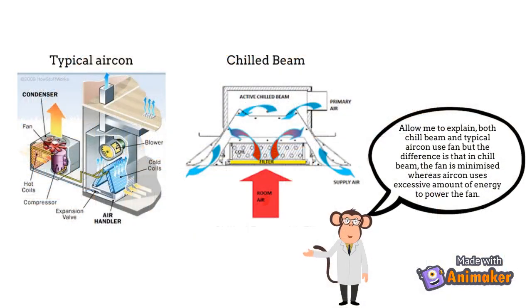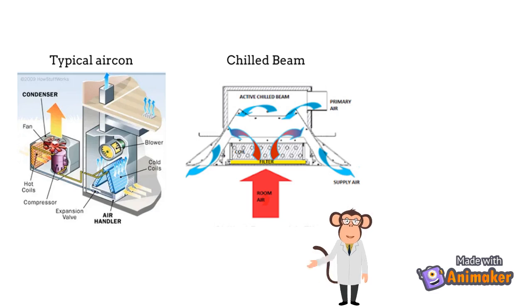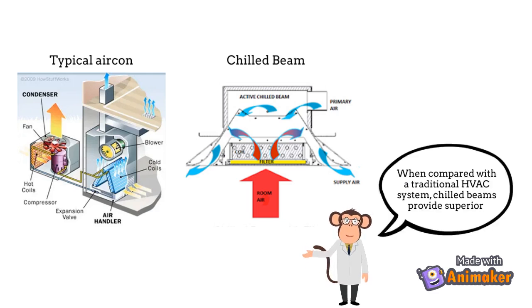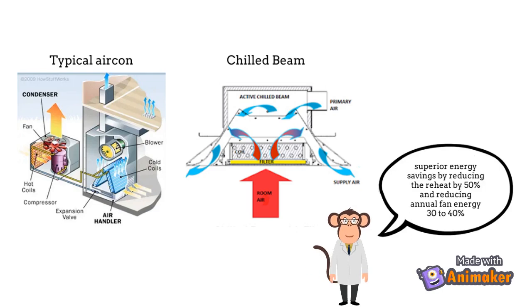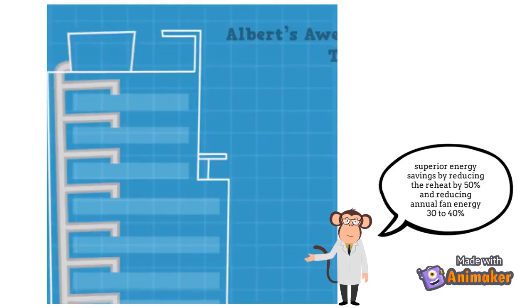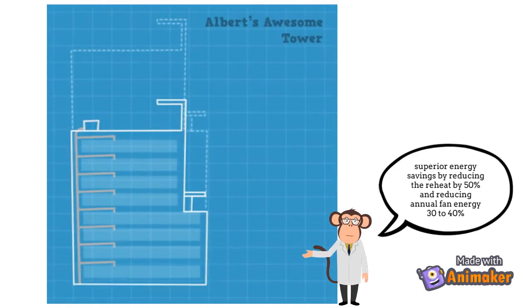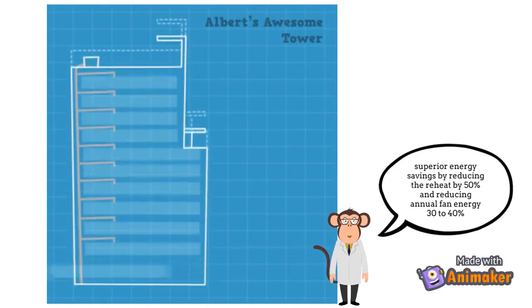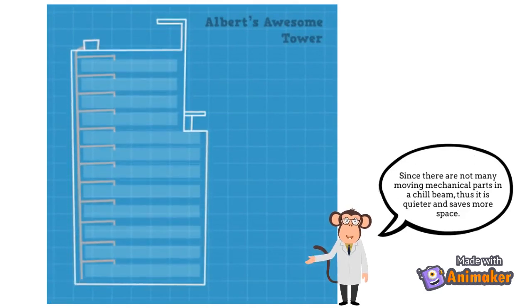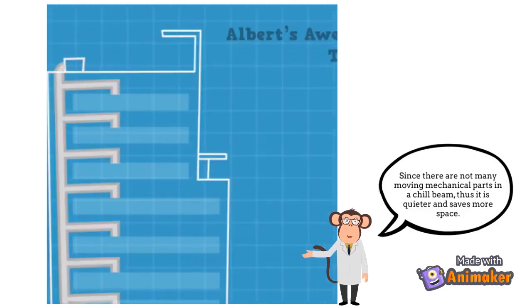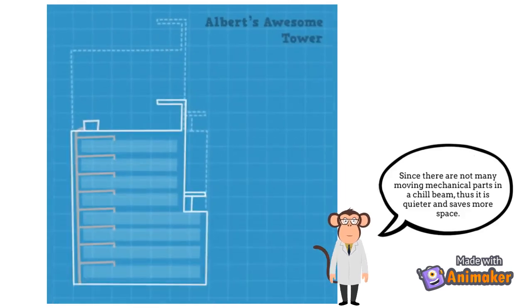Allow me to explain. Both chill beam and typical aircon use fans, but in chill beam, the fan is minimized, whereas aircon uses excessive energy to power the fan. Compared with a traditional HVAC system, chill beam provides superior energy savings by reducing reheat by 50% and reducing annual fan energy by 30 to 40%. Since there are not many moving mechanical parts in the chill beam, it is quieter and saves more space.